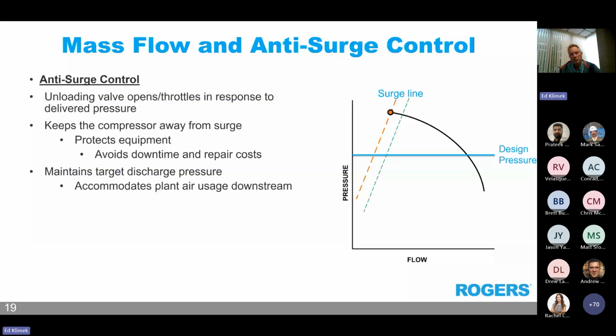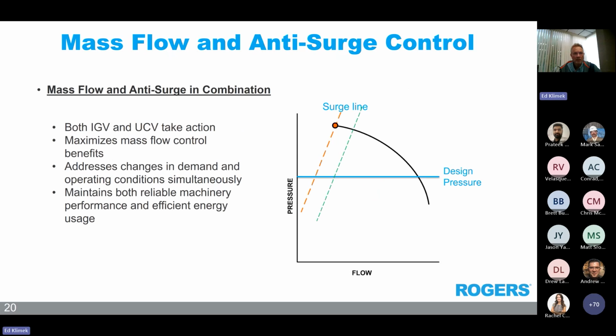The delivered pressure of the compressor, the anti-surge controls aid in maintaining this pressure, in addition to avoiding surge. In instances where the plant usage comes to a halt and the back pressure builds, the unloading valve opens to maintain the targeted pressure once the plant usage resumes. So that is mass flow and anti-surge working in combination. Well, just mass flow can be used, but the benefits of these two in combination are maximized when both are used.